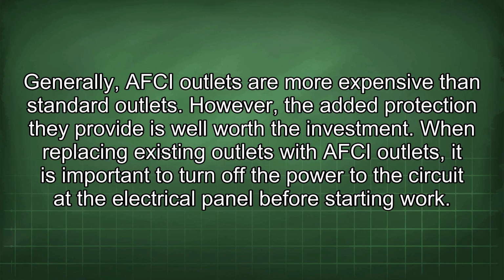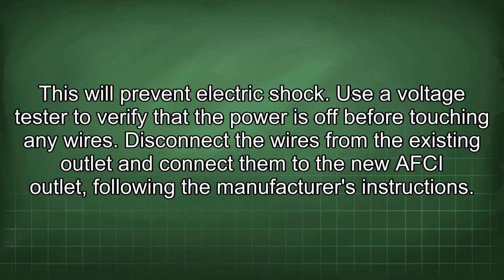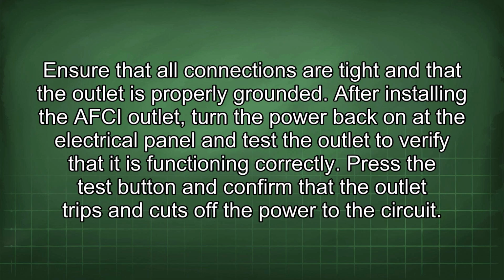When replacing existing outlets with AFCI outlets, it is important to turn off the power to the circuit at the electrical panel before starting work. This will prevent electric shock. Use a voltage tester to verify that the power is off before touching any wires. Disconnect the wires from the existing outlet and connect them to the new AFCI outlet following the manufacturer's instructions. Ensure that all connections are tight and that the outlet is properly grounded.